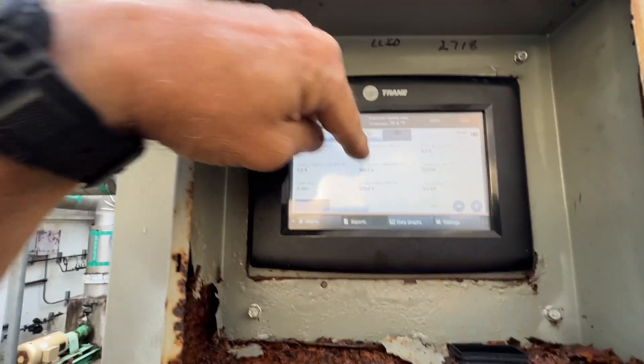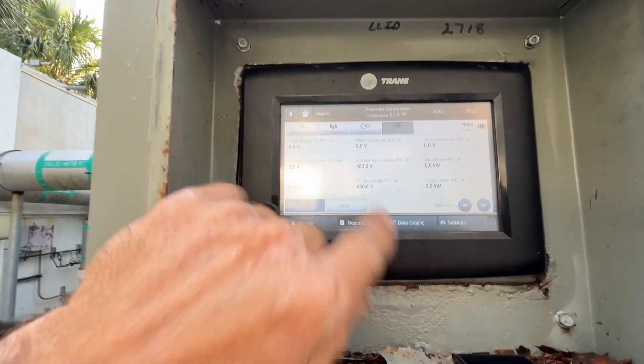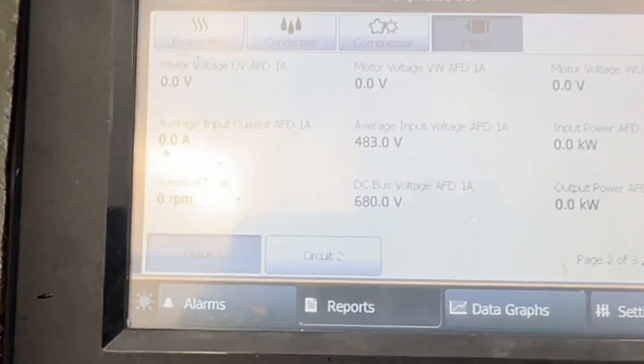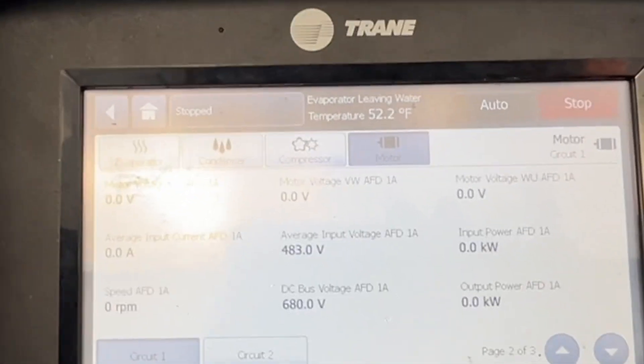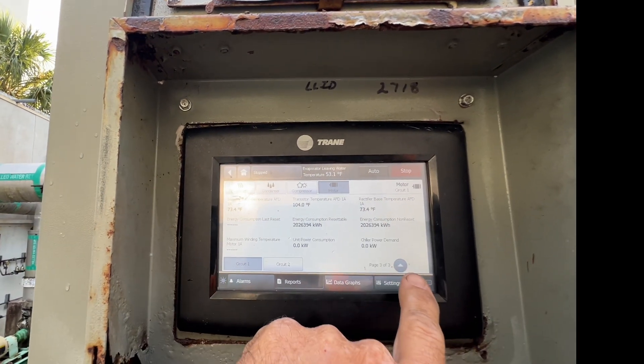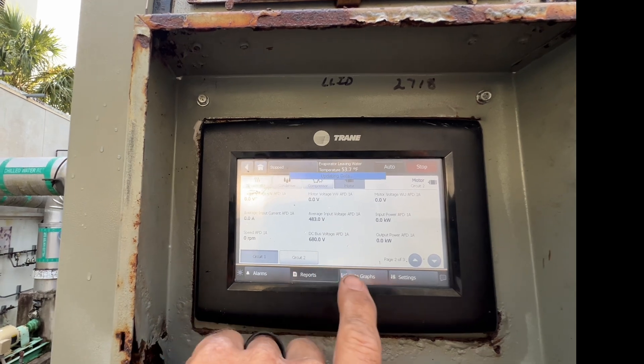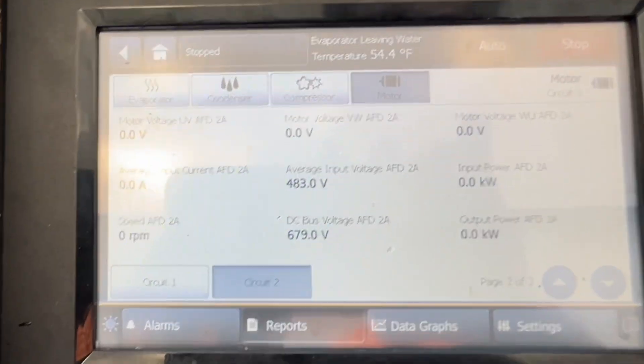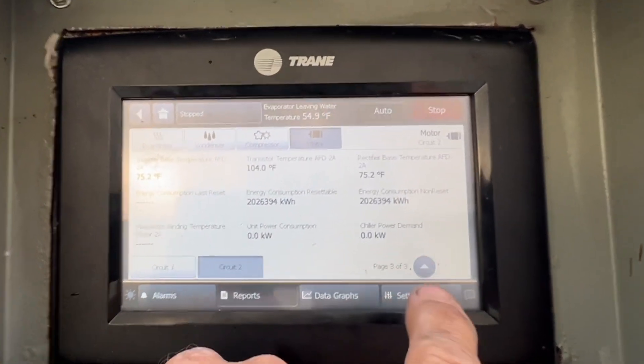So here is our AFD1 — we got 483 volts coming in and now our DC bus is back up to 680. I forget what we had in the last one but it was under 200 I believe. Circuit two is 483 and 679. So that's a good sign.